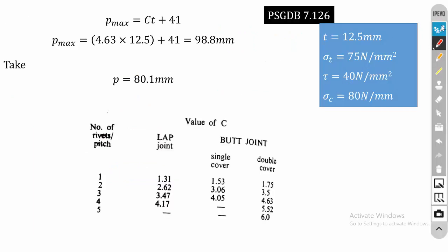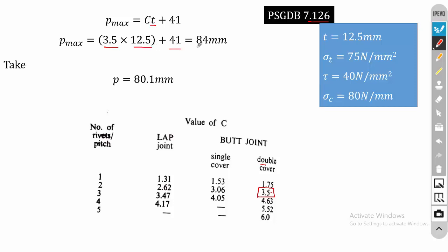We also check the maximum pitch per Indian Boiler Standard: p_max = c × t + 41 mm. For a double cover butt joint with i = 3, the constant c = 3.5. So p_max = 3.5 × 12.5 + 41 = 84 mm. The calculated pitch of 80.1 mm is less than 84 mm, so we adopt p = 80.1 mm.